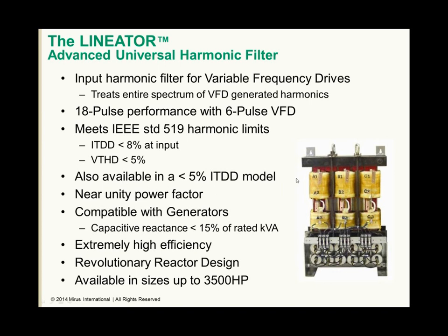We have models available that will provide less than 5% TDD in any application, and occasionally those filters are required when very sensitive loads are involved. But by treating the harmonics, we will restore the power factor to near unity. We ensure compatibility with generators by limiting our capacitive reactance to less than 15% of the rated kVA of the load. We're the most highly efficient of all the passive filters on the market. The key is in the design of our reactor, a multiple reactor on a common core, shared yoke configuration as shown here. And we have sizes that range from 5 horsepower all the way up to 3,500 horsepower.